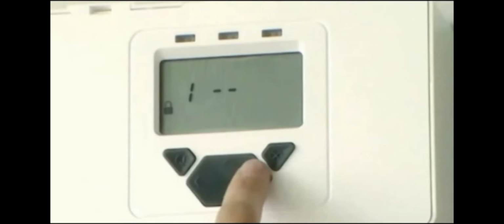You will notice there is a locked padlock icon showing that the system controller is in the User menu. In this menu, settings can be reviewed, but changes cannot be made to settings or to alignment. To align the system, access the Engineering menu by entering the passcode using the keypad. The default is 1, 2, 3, 4. The padlock symbol will be unlocked, and you will now be in the Engineering menu.